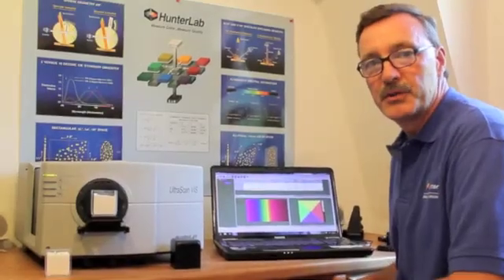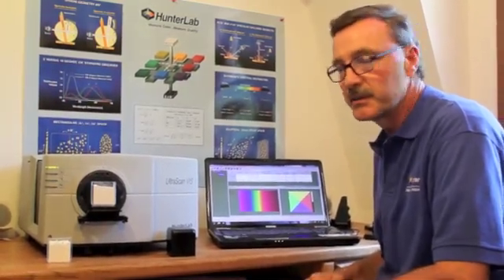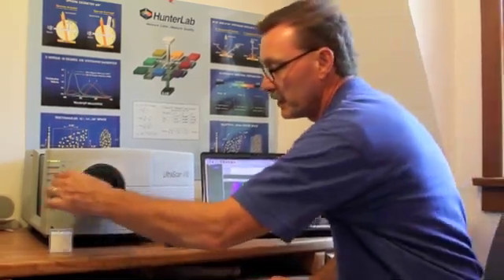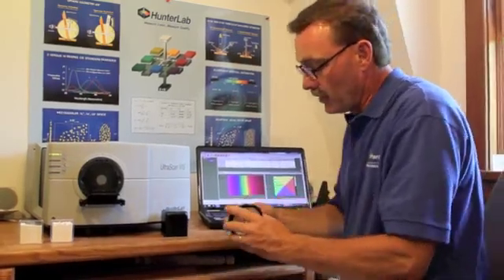HunterLab offers two versions of the Ultrascan. This is the Ultrascan VIS $17,000 system today used to measure powders. We can also measure small volumes or small quantities of powder with a powder holder, where you may have less than 1 cc of powder used primarily in product development.